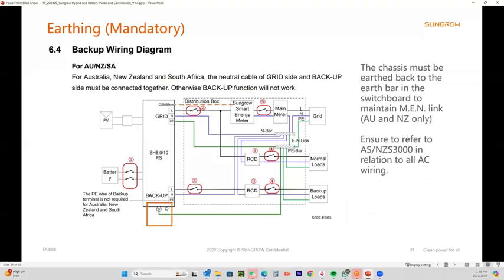Now the reason we need to do this is because the system, when it goes into off-grid mode, will completely decouple, including the earth. The internal earth of the backup is not connected. So you do need to earth the chassis back to the earth bar to pick up the earth neutral link. Otherwise your RCDs are not going to work. So yes, you do have to run an earth cable. As far as what size, just refer to the standards. That will tell you what size of earth cable to run. But you just run from the chassis back to your earth bar and you'll be fine.